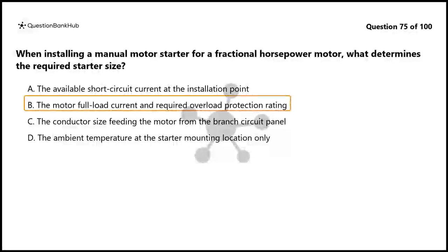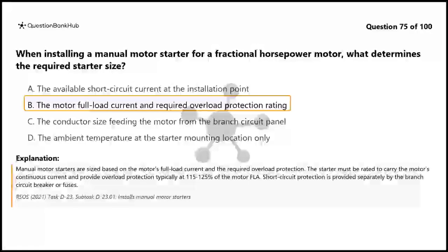The correct answer is B. The motor full load current and required overload protection rating. Manual motor starters are sized based on the motor's full load current and the required overload protection. The starter must be rated to carry the motor's continuous current and provide overload protection typically at 115 to 125% of the motor FLA. Short-circuit protection is provided separately by the branch circuit breaker or fuses.